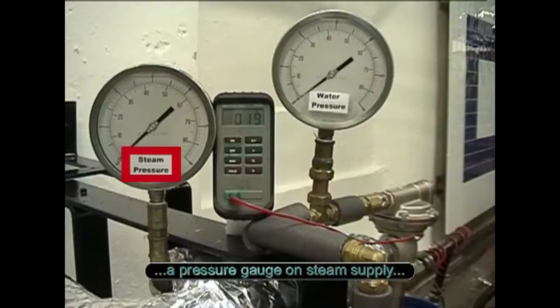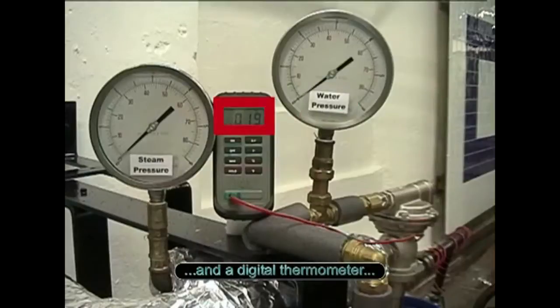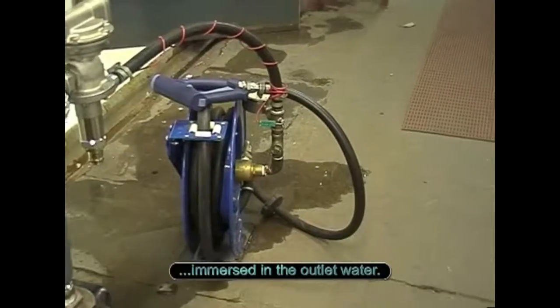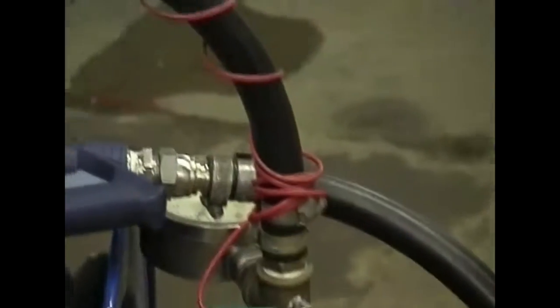The instrumentation is simple. A pressure gauge on the steam supply and on the water supply, and a digital thermometer immersed in the outlet water. The valve has been set to supply hot water at 60 degrees C.